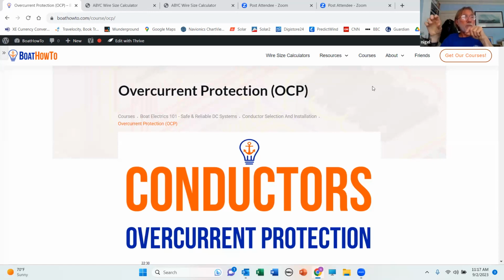But let's say we've got a piece of kit. It's a washing machine. And inside the washing machine, the hot conductor has the insulation worn through because of all the vibration when the washing machine's operating, and it's touching the frame of the washing machine. So now the frame of the washing machine is live. On the neutral side of our circuits, when you go to the outside of your house, you'll see there's a copper conductor going down to a metal rod that's hammered into the ground. Our neutral side is actually tied to that, tied to earth ground. So let's say we've got that short to the case of the washing machine.